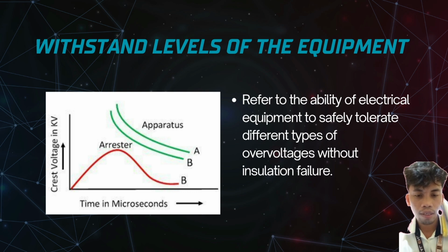Kana red or green sa curve. Say understanding the labels A and B in technical terms, this is usually present the different types of standards test. So for the curve A, chop wave, this represent the equipment's response to very fast high energy surge like a direct lightning strike. In curve B, full wave or BIL or basic insulation level, it is standard rating used to define equipment ability to withstand lightning surge under normal condition.